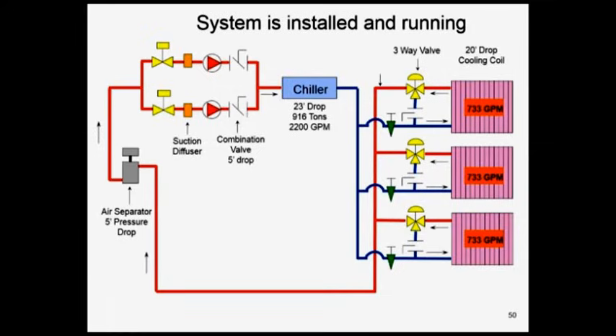So you say, wait a minute, Chris, if I know this, the tubes are clean, we've got to assume the tubes are clean. Yes, we'd have to assume that. But assume the tubes are clean, and we know this, then we could give you the pressure drop at any other flow rate. Or we could give you the flow rate if we know the pressure drop. Wow! Are you saying to me I can make the chiller barrel into a circuit setter or a flow meter? Yes. And this is what's neat when you start learning some of this and putting it together. So let's do that little game.